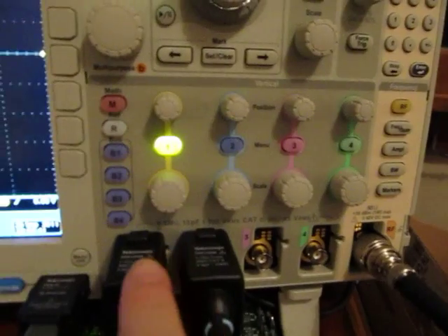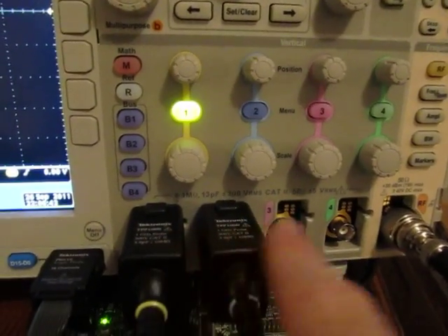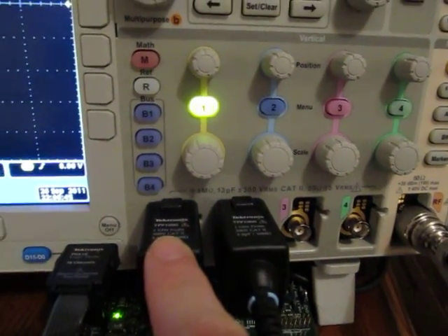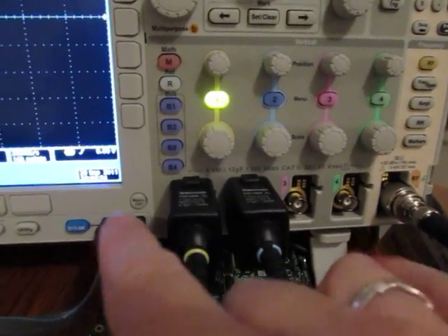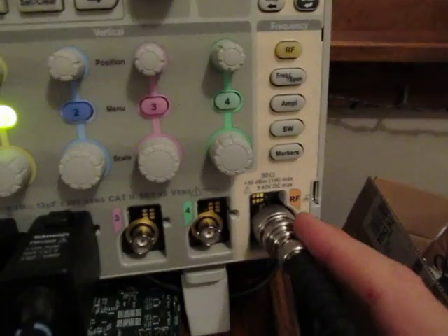Okay, this video is going to take, well, 5 minutes or so to talk about what this new Tektronix MDO, Mixed Domain Oscilloscope, is all about. Basically, it is a four-channel analog, digitizing oscilloscope. These channels will either be 500 megahertz or 1 gigahertz of bandwidth on all four channels, 16 digital channels, 20 meg of memory behind all of those channels, but then also adding either a 3 or 6 gig spectrum analyzer to the box.